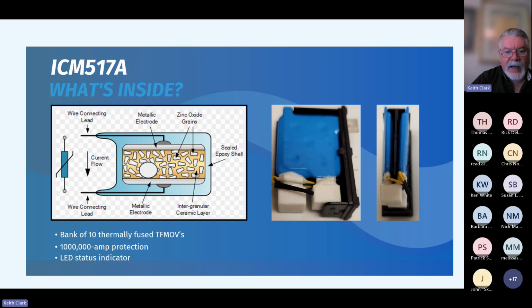If it does not, and this is to simulate that some of those things got fused together, there was enough heat there to cause a little damage, and it fused some of those grains together. Well, it's slightly degraded, but there's plenty of zinc metal oxide grains left to continue to take punishment and take the hits until that thing is finally used up, and then it moves to the next TMOV. So you've got a bank of 10. So this thing will take punishment for a long, long time.